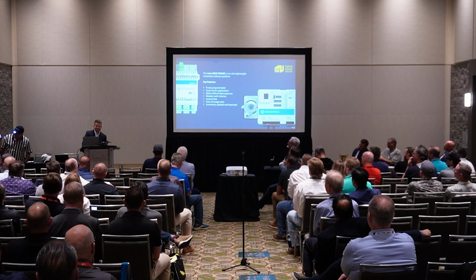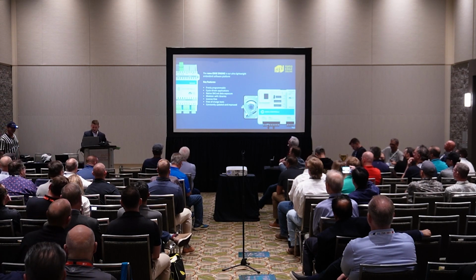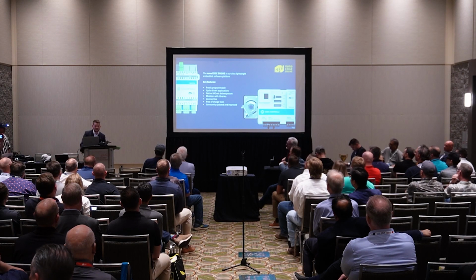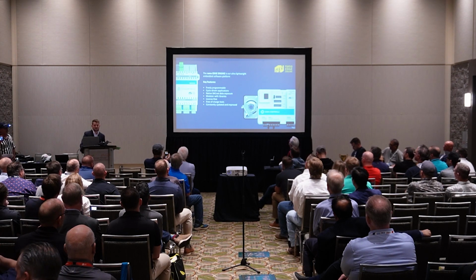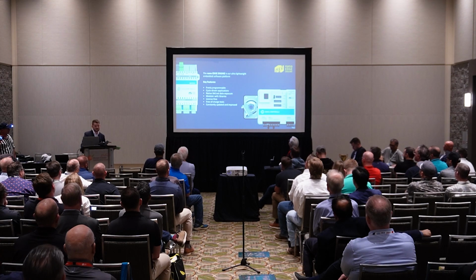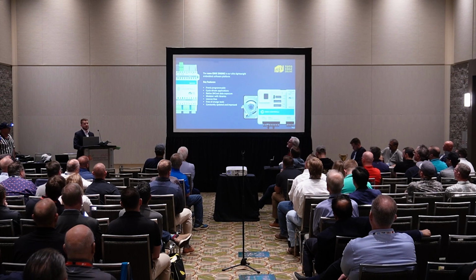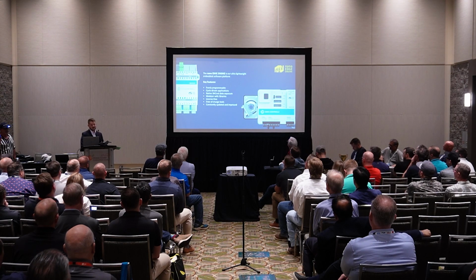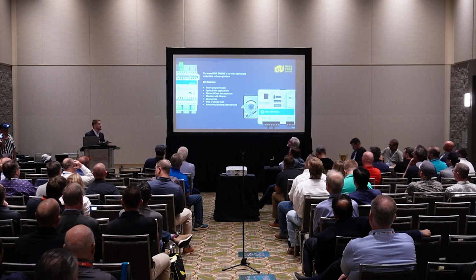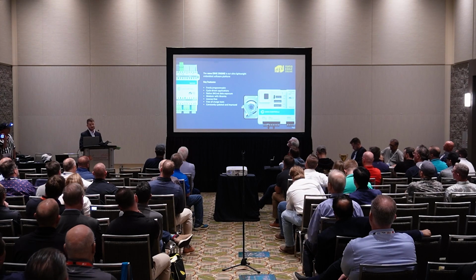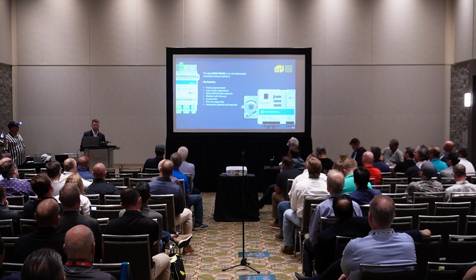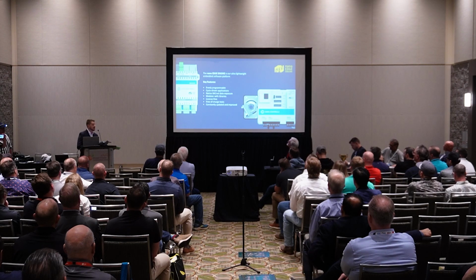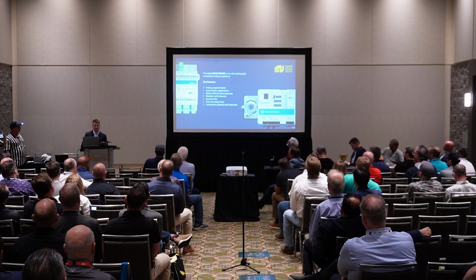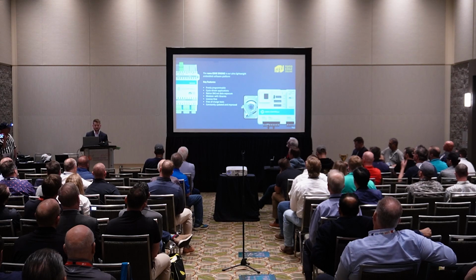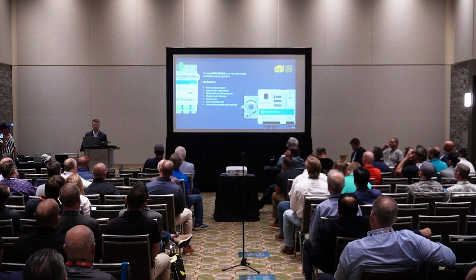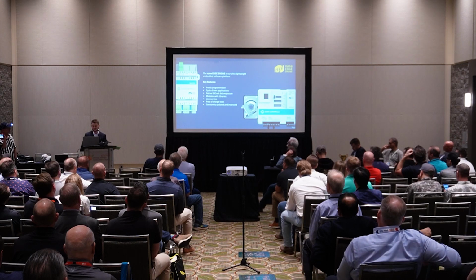Nano Edge Engine is an ultra-wide software platform that we put into our controllers. Some key features: freely programmable, you can run multiple applications in time cycles up to 100 milliseconds. Without going too technical, you can control lights, HVAC, multiple applications on those controllers. They're native with BACnet, modular with libraries, license-free, so there's no license for those controllers. They're only limited by the number of data points you can expose. We have free-of-charge tools, and we constantly update those controllers with a lot of improvements.